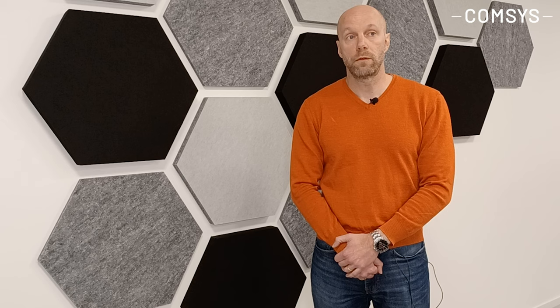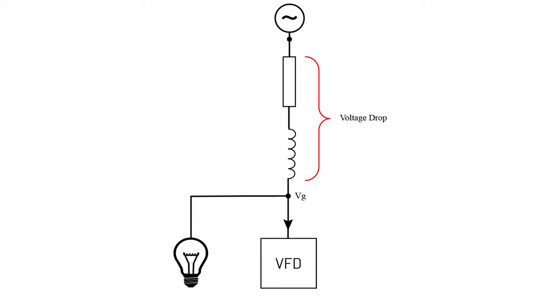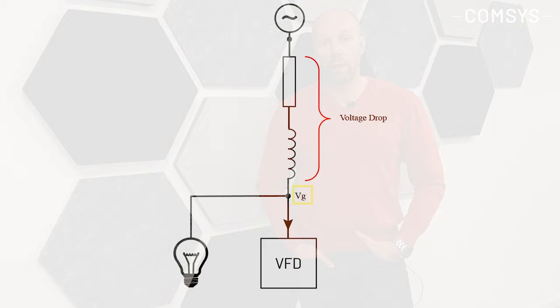If we go back to the source model and the load, we will see that we have a voltage drop over the inductor and over the resistor, and this voltage drop is what is creating the problem. Because if we look at point Vg — the voltage at the secondary of the transformer, your incoming feeder to the facility, or the outlet in the wall — we will see that since we have a voltage drop over the resistance and the inductor, we will actually have a distorted voltage.